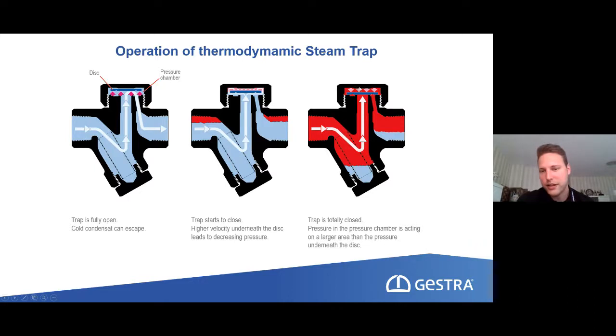And then we have a little air bubble here on top of the valve disc. An air bubble doesn't condense. So as soon as the steam trap has come into contact with air internally, it will be blocked for a very, very long time, as long as the air has not disappeared, maybe via this thread, or condensed somehow, or maybe through small leakages because the trap is damaged or something like this. This steam trap will be closed. So the second basic requirement is also not sufficiently fulfilled with this kind of steam trap, but it is cheap. So this is something you have to wait out. But if you want a properly working steam system, I would not recommend this kind of steam trap.